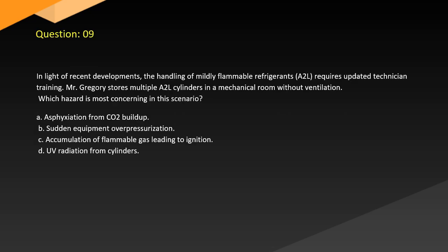Question 9. In light of recent developments, the handling of mildly flammable refrigerants requires updated technician training. Mr. Gregory stores multiple R-32 cylinders in a mechanical room without ventilation. Which hazard is most concerning in this scenario? A. Asphyxiation from CO buildup. B. Sudden equipment overpressurization. C. Accumulation of flammable gas leading to ignition. D. UV radiation from cylinders.